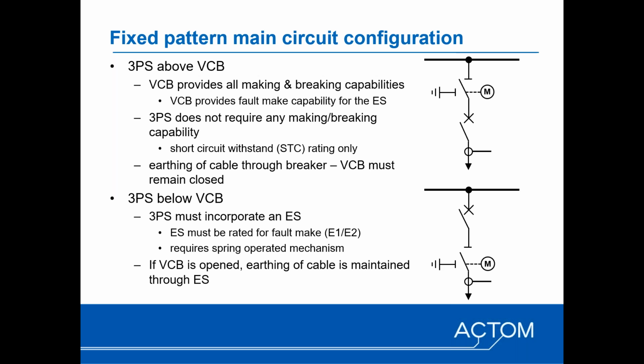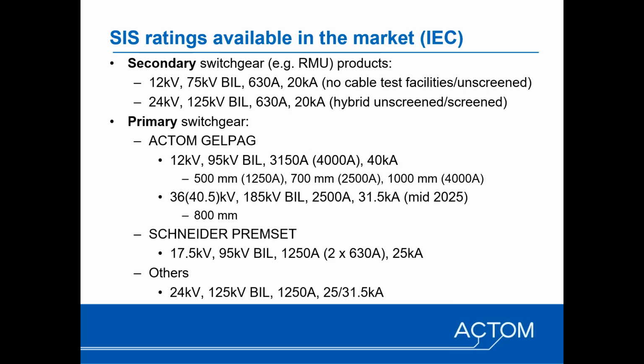However, when you have the bottom configuration, you can no longer rely on the circuit breaker to do all the making and breaking, because when you're closing the switch, the earthing switch is downstream of the circuit breaker, and therefore it's required to have a making capability, if it is of course rated E1 or E2 in accordance with 62271-102, which requires it to have a short circuit making capability. So then you need a special operating mechanism, typically a spring operating mechanism, to ensure that the speed of the earthing switch and the closing of the contacts are suitable for that making operation. So economically, it may not be as viable. And as I say, ultimately, this is something that should really be left to the manufacturer and not predetermined or specified by the user, because functionally, they are equivalent in terms of the user.